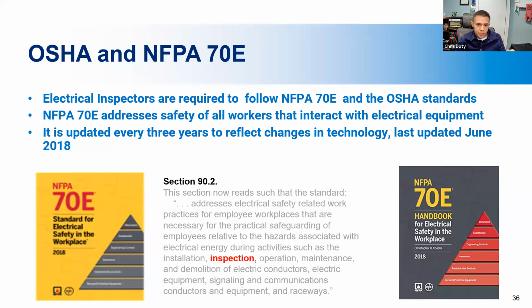So inspections are required to follow NFPA 70E, which is the standard for electrical safety in the workplace, and of course OSHA requirements. Everything has to follow OSHA requirements. But NFPA 70E has traditionally been for electrical workers, and now has been updated to include inspections as well. So inspectors have to comply with the standard. And as part of this, an initial risk assessment is required. If the electrical inspection involves removing covers, the assessment will determine if PPE is required or if other methods of risk reduction are required.